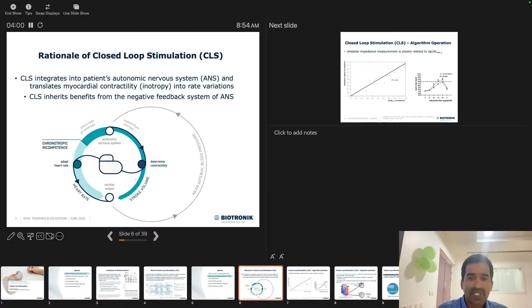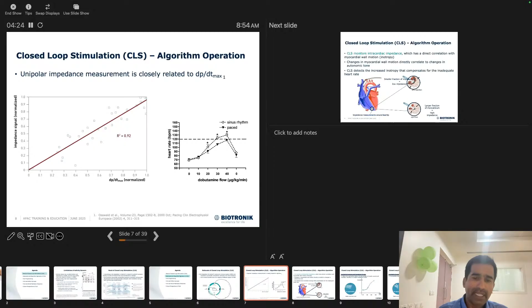It gives minute impulses of around 0.03 volts. In a duration of 300 milliseconds, it gives 8 pulses, so 8 coupling intervals in a unipolar mode, and then it takes the impedance. As we all know, during pre-ejection, because there is an overload of blood, the impedance would be low. And when we have ejection, when the contractility is happening, the impedance will be more, because a lot of tissue is surrounding the lead tip.